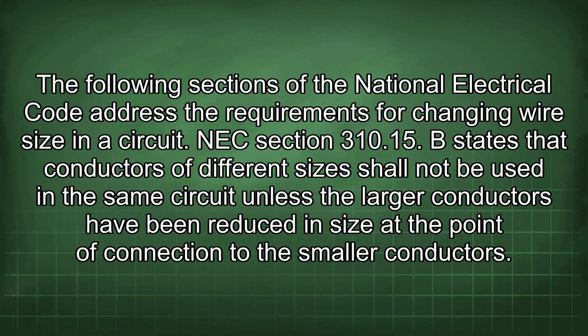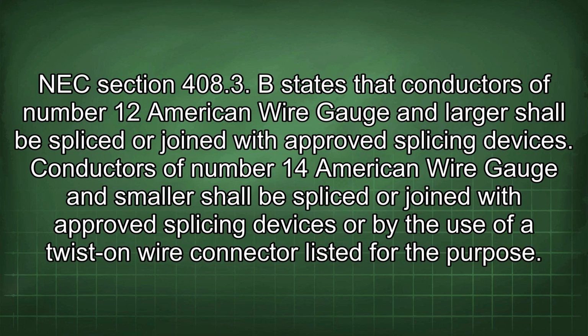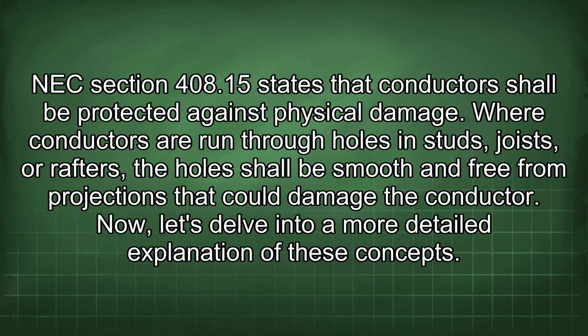NEC Section 310.15 states that conductors of different sizes shall not be used in the same circuit unless the larger conductors have been reduced in size at the point of connection to the smaller conductors. NEC Section 408.3(B) states that conductors of number 12 American wire gauge and larger shall be spliced or joined with approved splicing devices. Conductors of number 14 American wire gauge and smaller shall be spliced or joined with approved splicing devices or by the use of a twist-on wire connector listed for the purpose. NEC Section 408.15 states that conductors shall be protected against physical damage. Where conductors are run through holes in studs, joists, or rafters, the hole shall be smooth and free from projections that could damage the conductor.